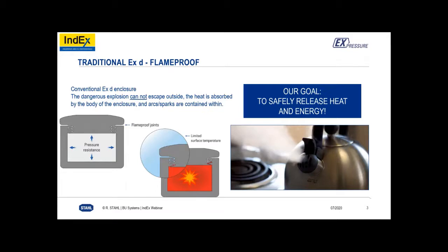Yes. So traditionally, for traditional EXD, we're looking at a box that is going to absorb the heat out of the explosion and contain the arcs and sparks within the enclosure. Now, what you're saying is that R.Stahl has come up with another method that could perhaps be better than a standard EXD box. So I'm going to go to the next slide just to show people really quickly what we're looking at when we're dealing with EXD.